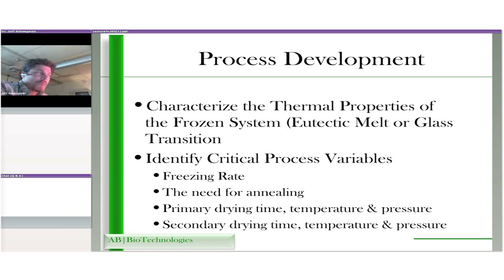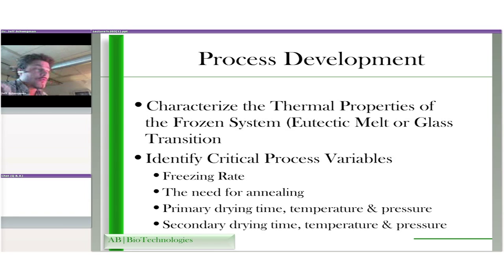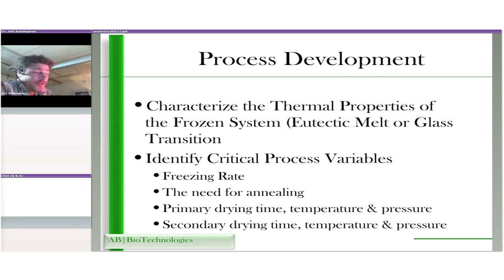Again, in this slide, as I mentioned, the first thing we're going to do — any time a sample comes into my lab — the first thing I will do is the thermal characterization. So I'll do the DSC and the freeze dry microscopy so I know: am I dealing with a eutectic system, a glassy system? And in many cases, it may be a mixed system with a combination of both those phases.